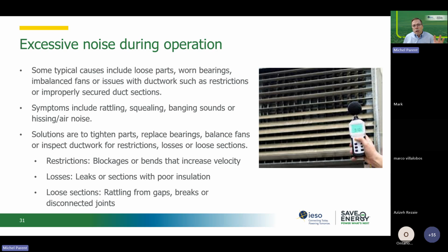Excessive noise during operation. Again, I'm going to let you read that one, but there are a few things that are not in here that I see during recommissioning. Sometimes excessive noise is due to fire dampers partially closed. I've seen dampers in air handling units that were all closed at the same time because of improper installation of the actuators. They were in reverse order. And then you get this really thumping noise from your HVAC system. So if you hear a lot of excessive noise, especially air noises, it's usually linked to velocity.